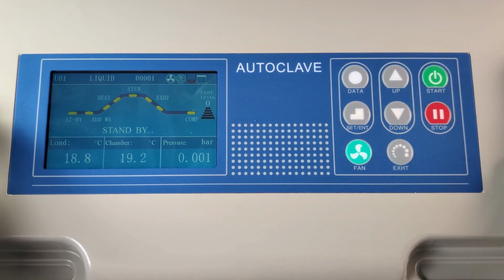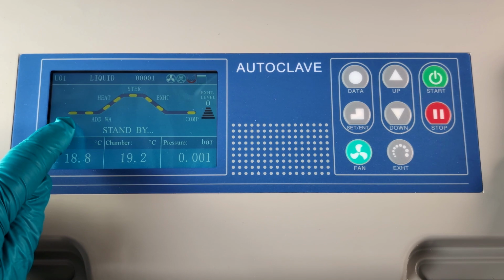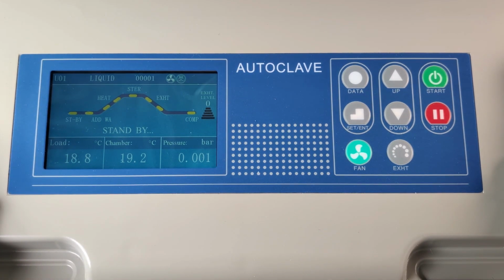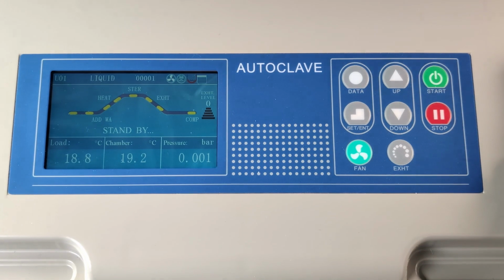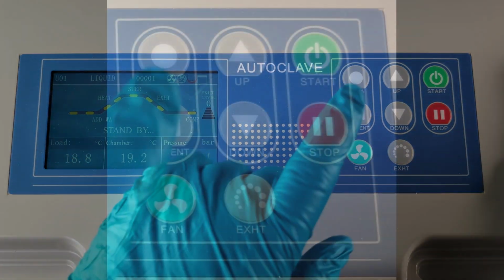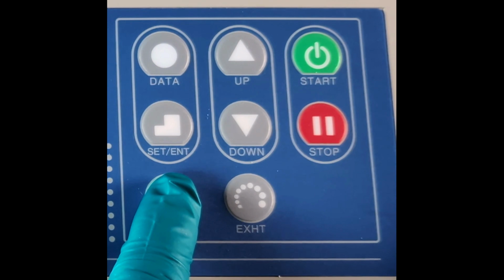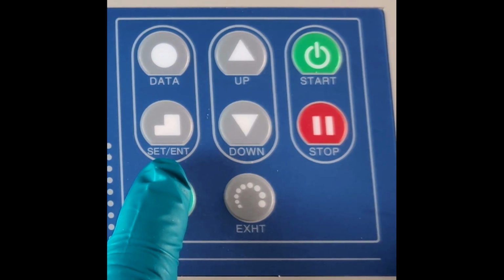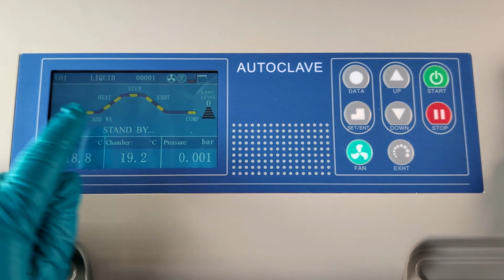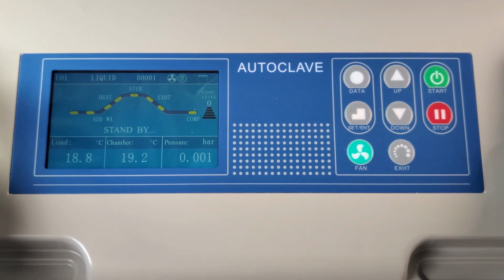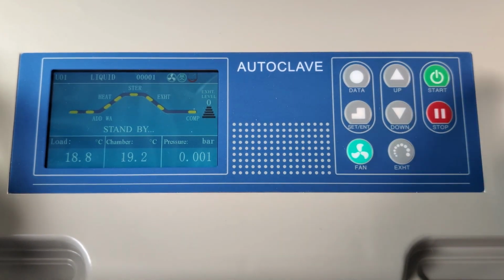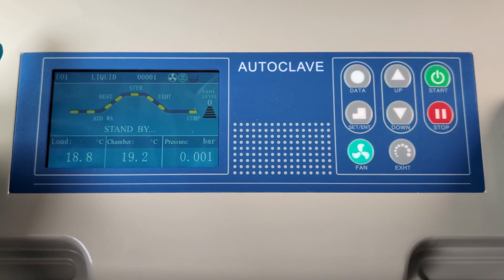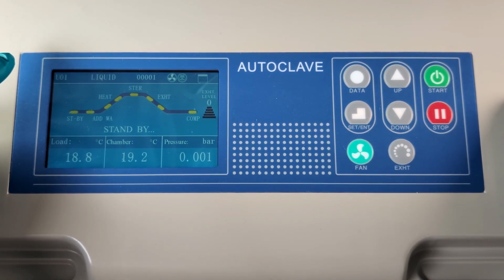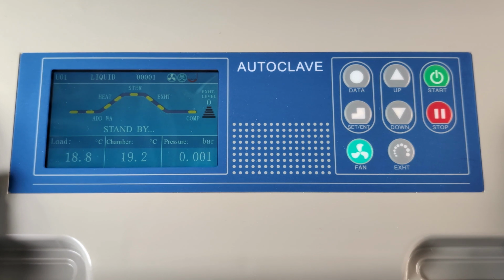So if we look at this liquid cycle, you'll see that there's standby flashing at the moment, so the autoclave is in standby mode. But of course it needs water. So the next thing would be for using these buttons here, to get the automatic water fill working. Once you've done that, the add water part will start flashing, and will do so until it's got enough water inside. It'll then, when you press the start button, go on to heat. At the heating stage, first of all, it gets up to boiling point at around 100 degrees centigrade, and at that point, the steam pushes out all the air.